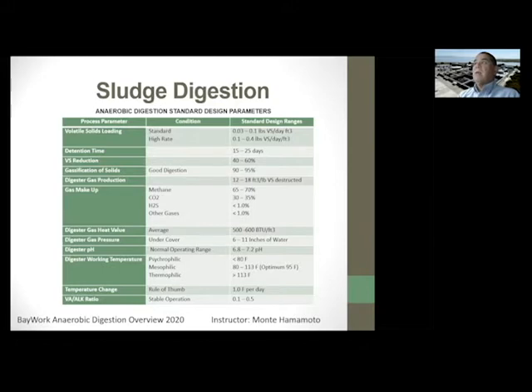The detention time is 15 to 25 days. How much volatile solid reduction you should have after those 15 days should be 40 to 60%. Gasification of your solids—this is breaking down the solids and the methane gas formation. And then digester gas production, how much digester gas will be produced, that's methane basically, and CO2, for every pound of volatile solids that is destructed.